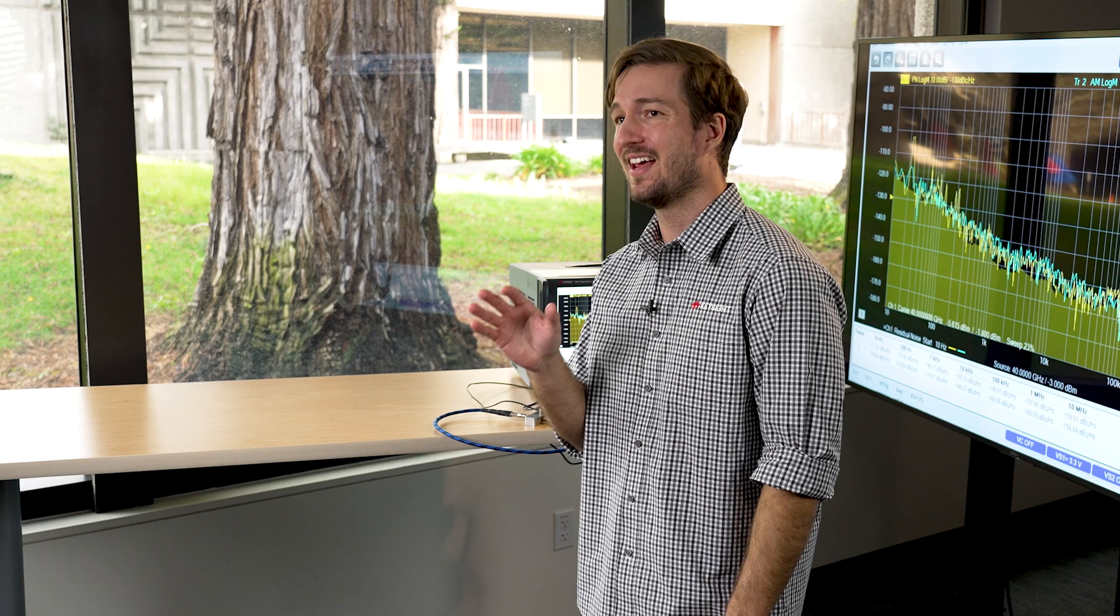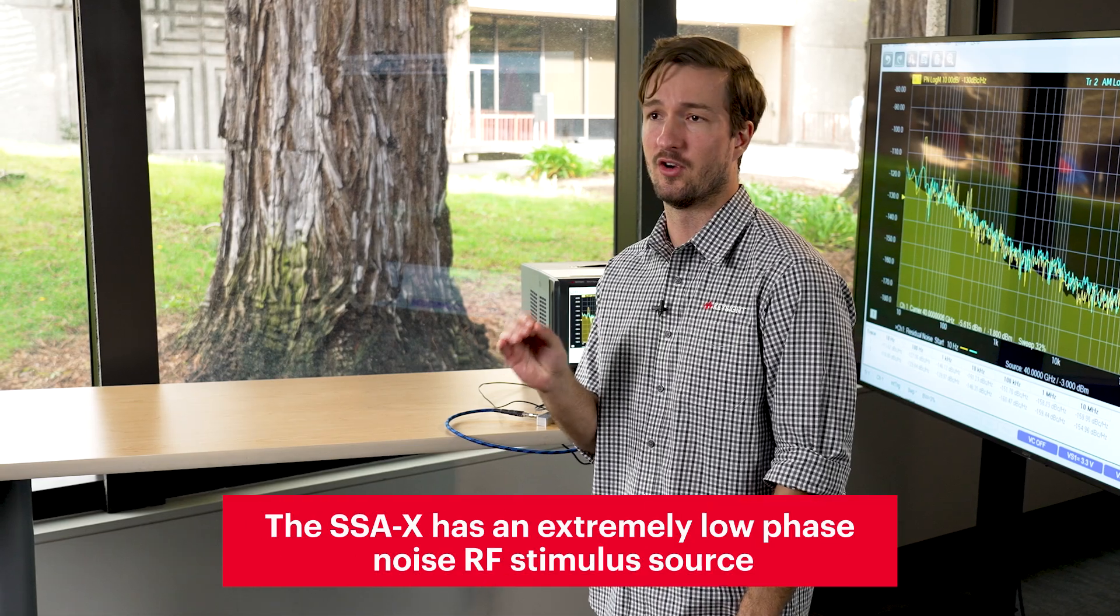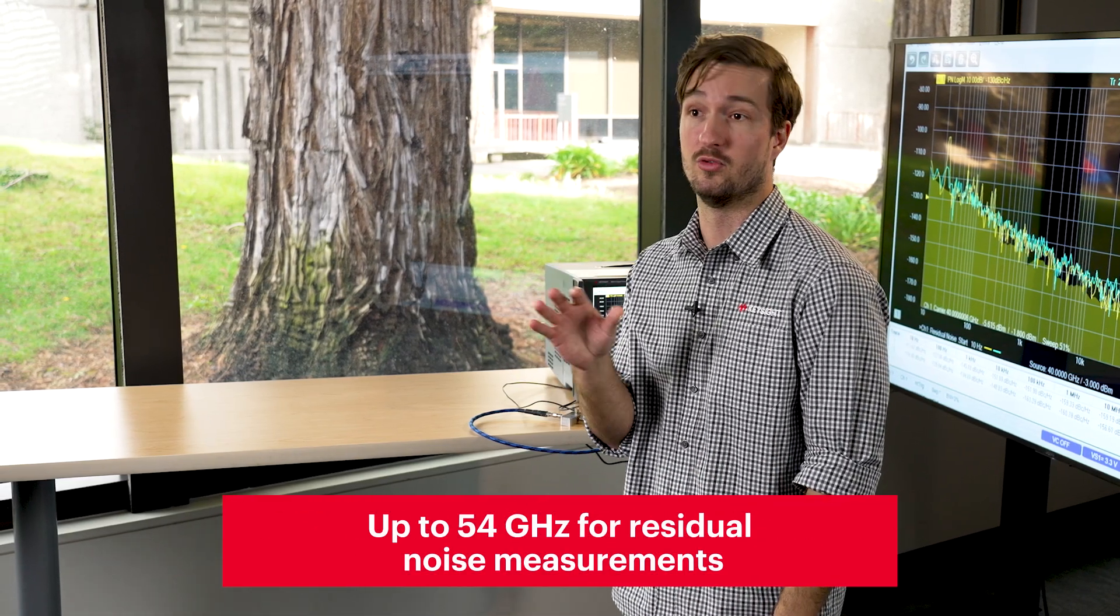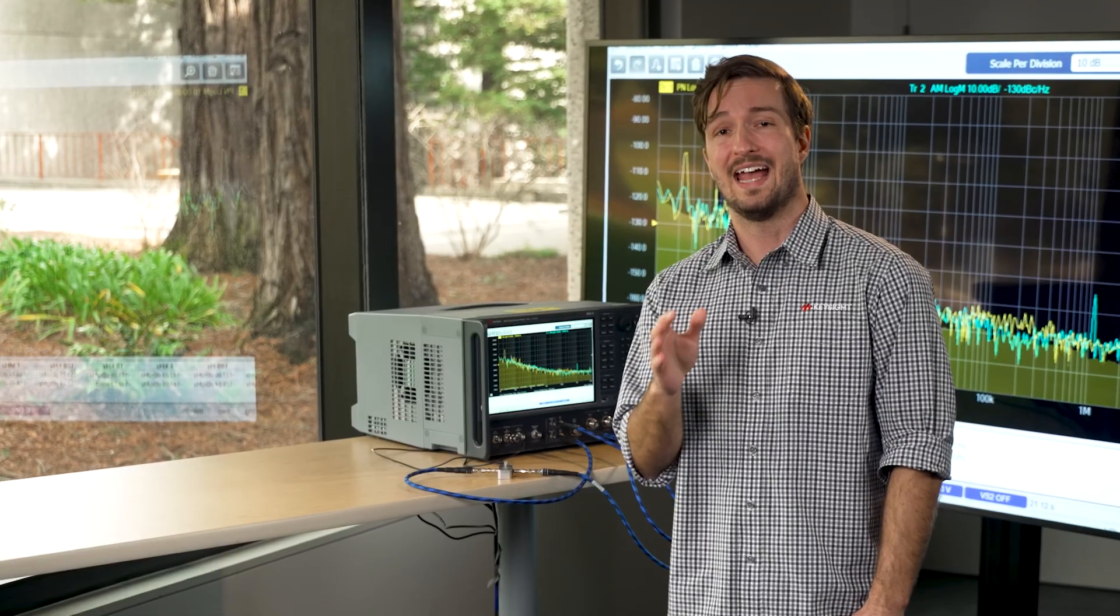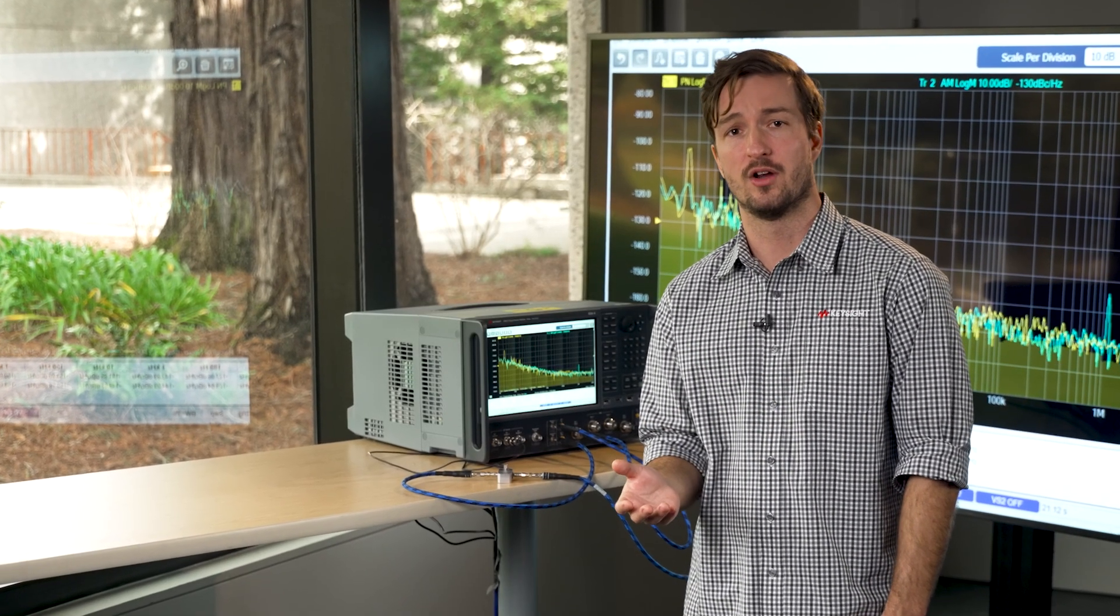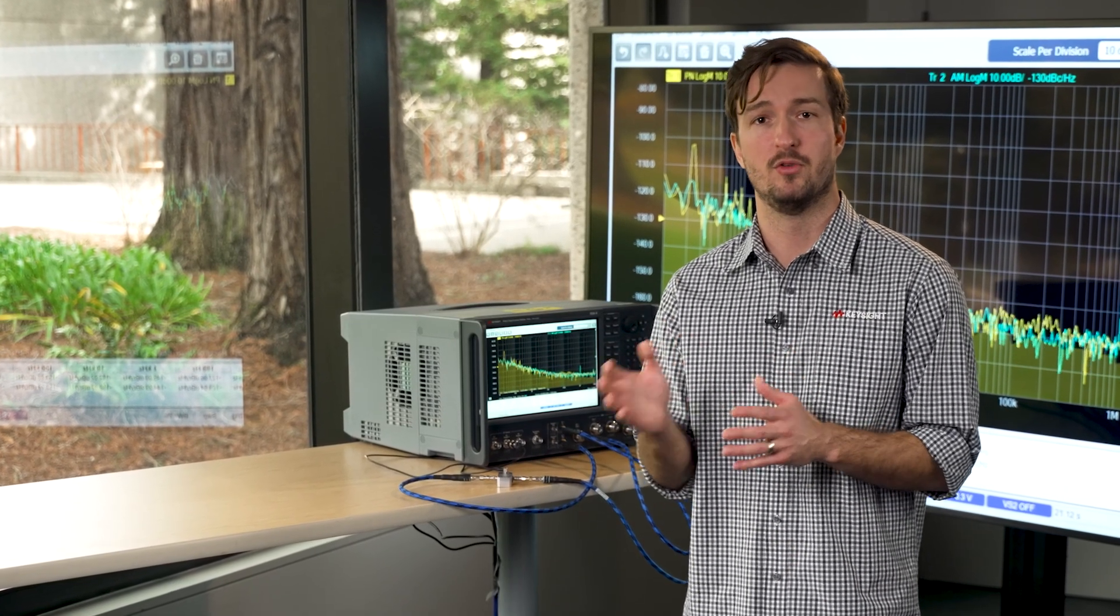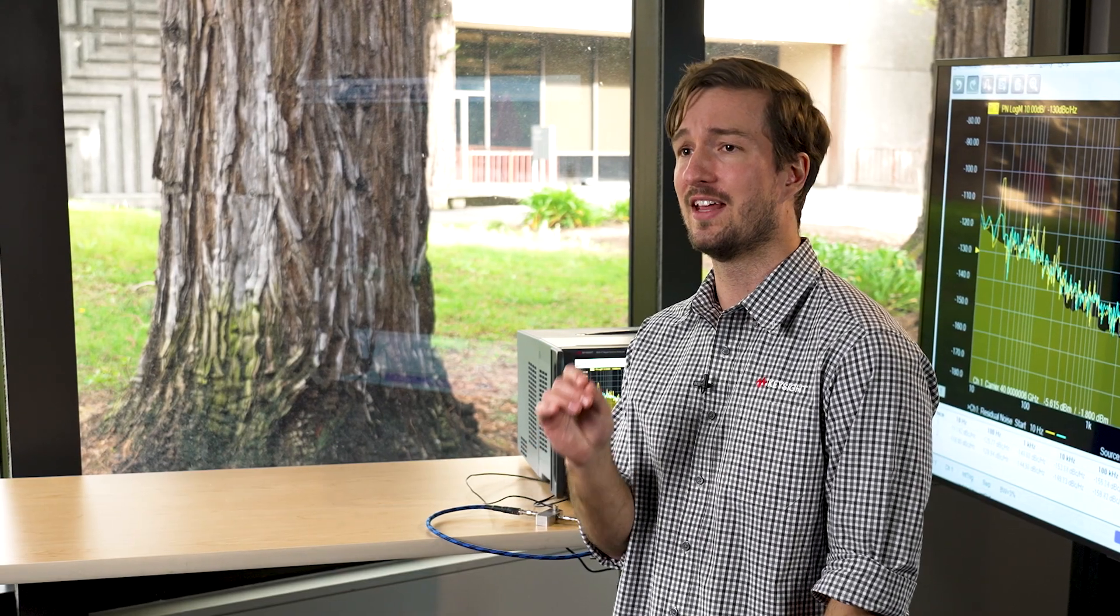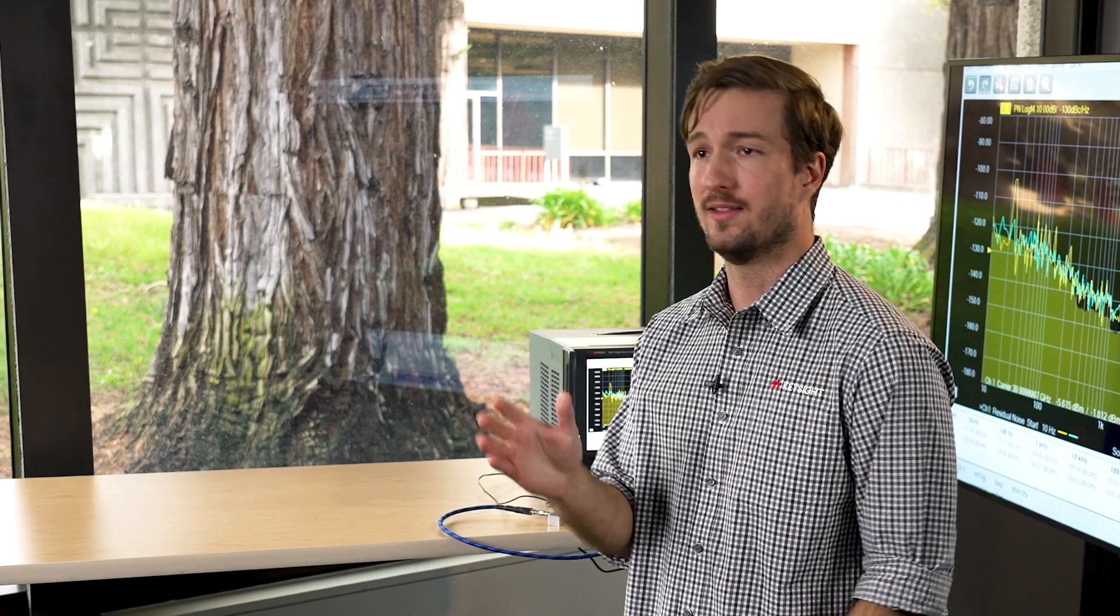The SSA-X has an extremely low phase noise RF stimulus source that goes up to 54 gigahertz for residual noise measurements. With the SSA-X, any noise from the RF stimulus source is a common mode signal into two receivers and ratioed out of the measurement such that the additive noise of the multiport DUT is the only thing that's measured.